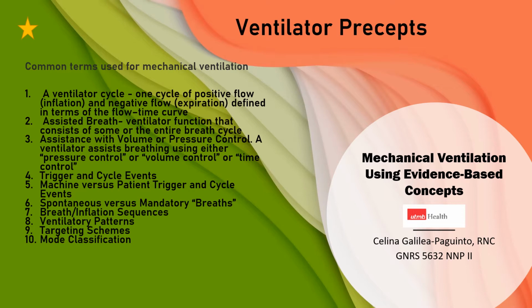Number 8, ventilatory patterns. These are sequences of inflations and or spontaneous breaths: the CMV, IMV, or CSV with a particular control variable, whether it's volume or pressure, for the ventilator inflations. There are 2 control variables and 3 breath sequences, totaling 5 basic ventilatory patterns.